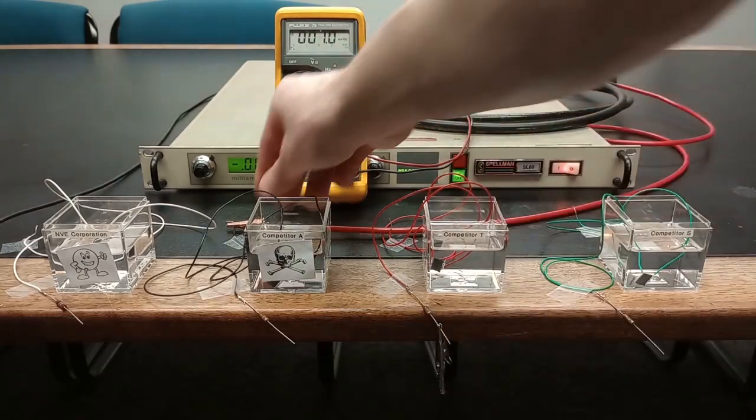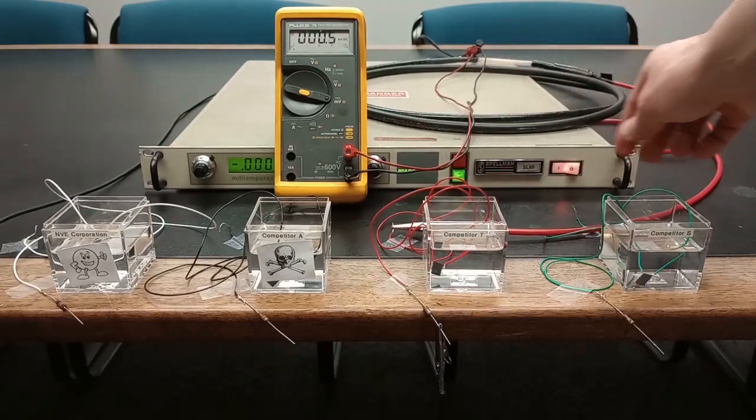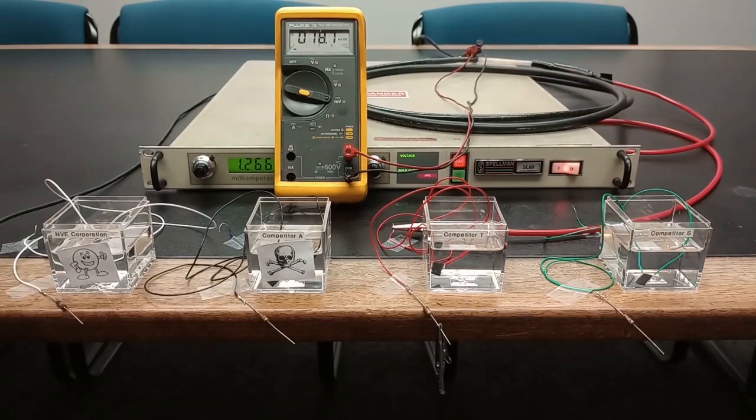Unfortunately competitor T doesn't fare much better with visible arcing across the resistor. That means the isolation barrier of the isolator failed and the high voltage is showing up at the resistor terminals showing the safety has also failed.